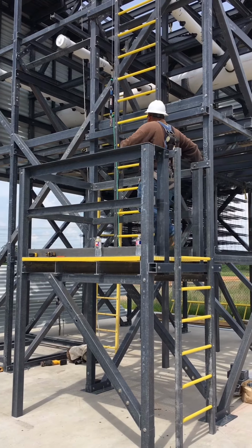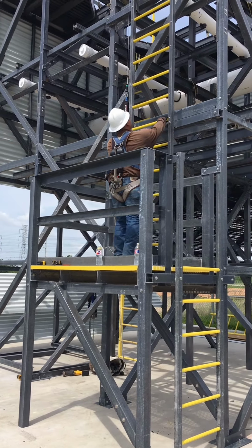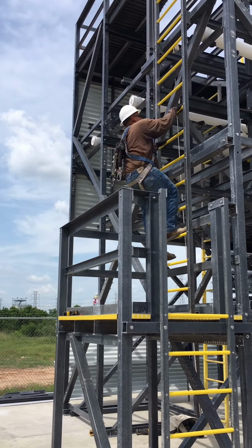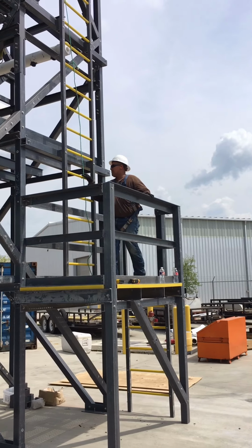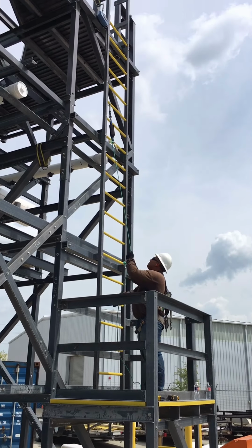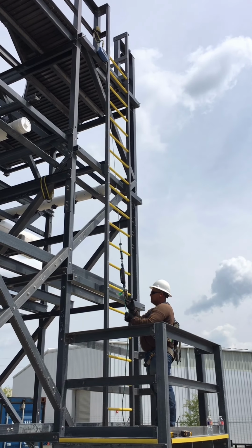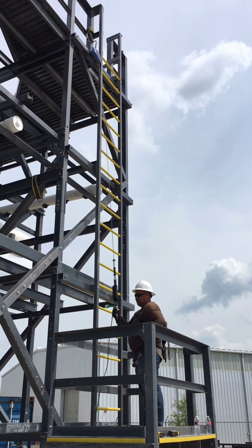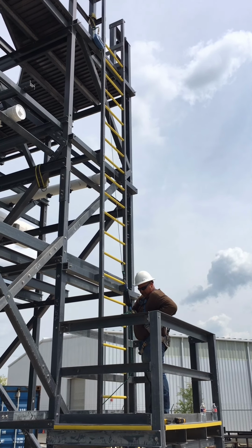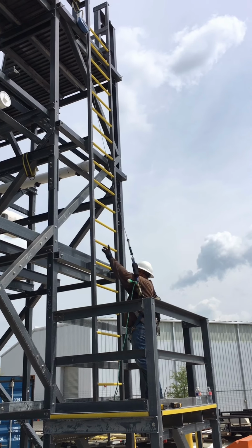When using a fixed ladder, you should first inspect the ladder to ensure it is safe for use. Evaluate the ladder to determine if fall protection will be required. If you determine that fall protection is needed, you will install a self-retracting vertical lifeline. It is acceptable to use a ladder without fall protection one time for the purpose of installing fall protection.